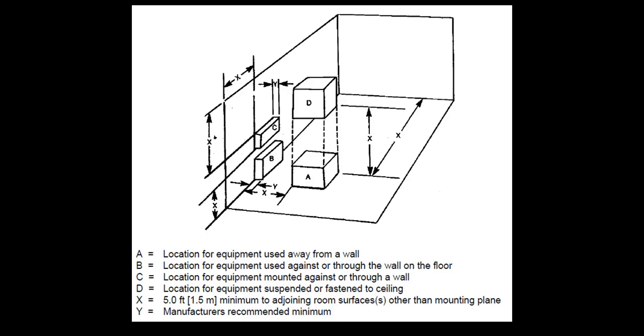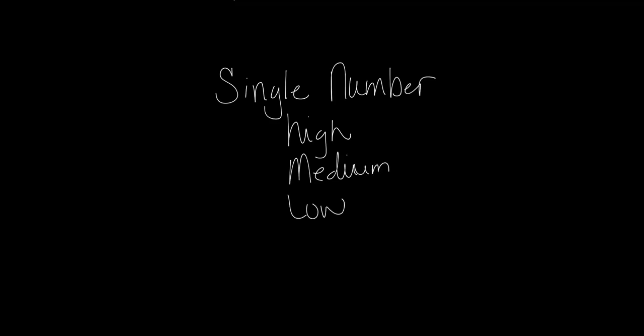And the microphones within the test chamber are basically going to record everything. Discharge, radiated, inlet, all noises and vibrations coming from the unit will get recorded at once and put into a single number. We publish this single number for high speed, medium speed, and low speed, and it is recorded in sound power. The issue with fan coil units, and the reason 350 is around, is that basically it is just a complete and total raw sound power number for a fan coil unit. It's everything. It's all the different types of sound into a single number.